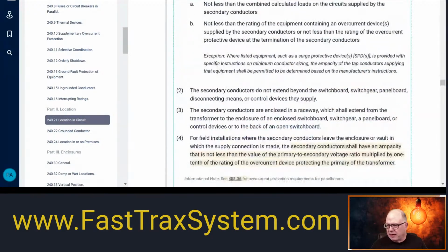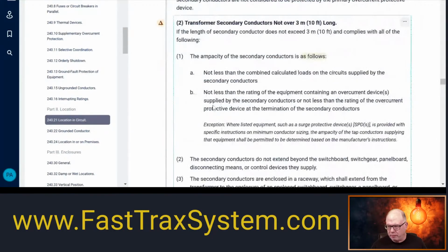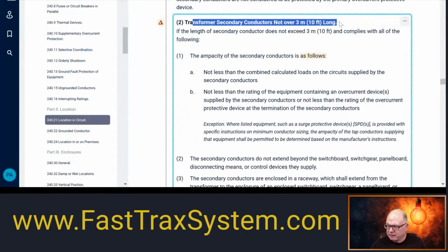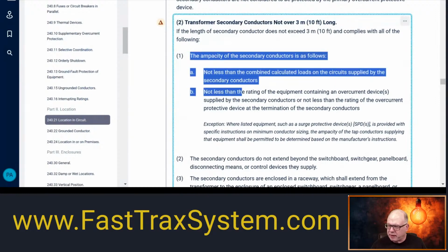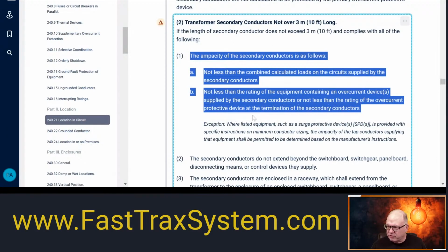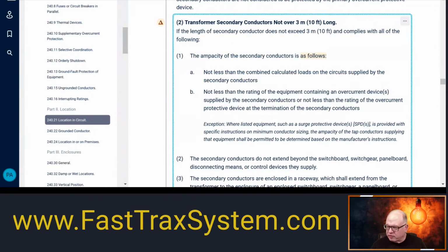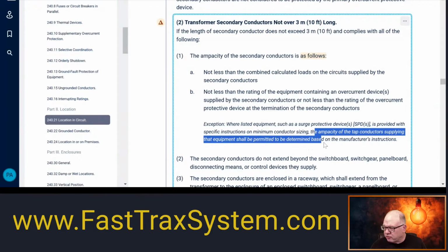All right, so let's get back to our lesson here. So we're back here at the 10 foot. So we made sure our ampacity is fine. Now, we do have an exception. The exception says where listed equipment such as surge protected devices is provided with specific instructions on minimum conductor sizing, the ampacity of the tap conductor supplying that equipment shall be permitted to be determined based on the manufacturer instructions.